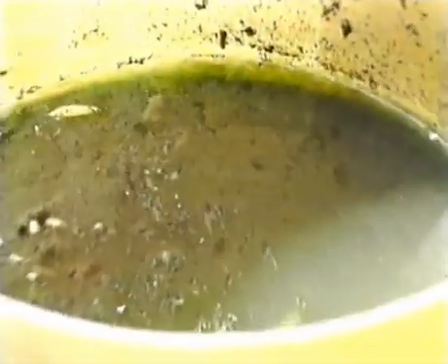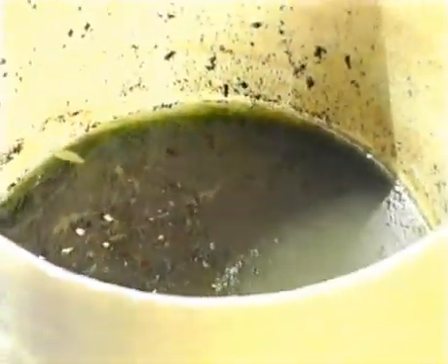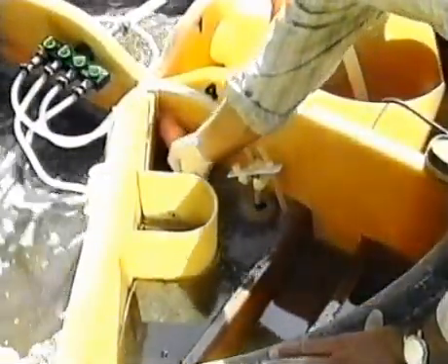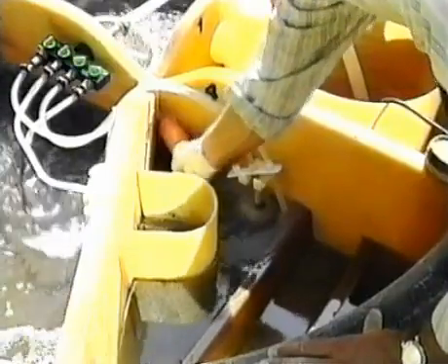The settler is linked to the oxidation chamber by a passage protected by a damper tube. This tube reduces the turbulence of the aerated mixture and accompanies the excess sludge toward the airlift, which is the recycling aspiration point.